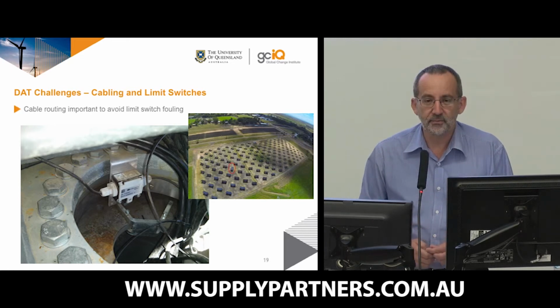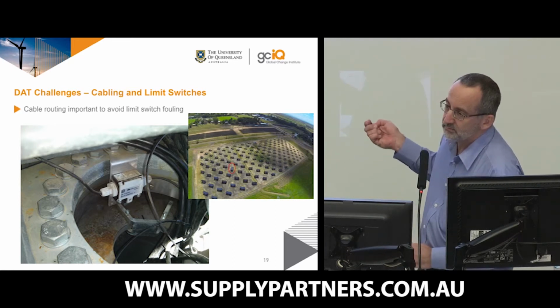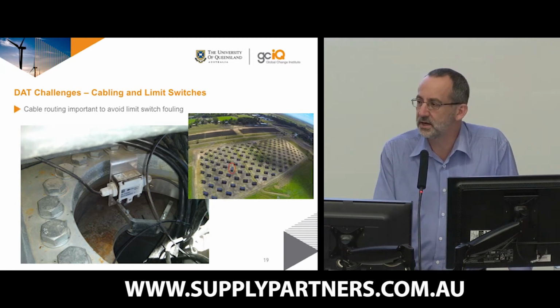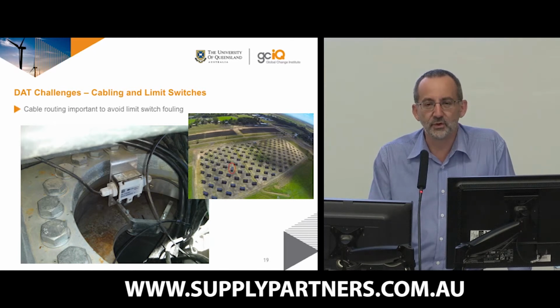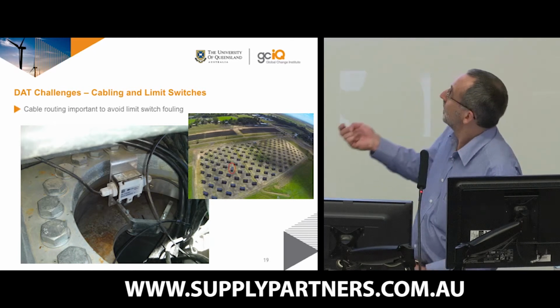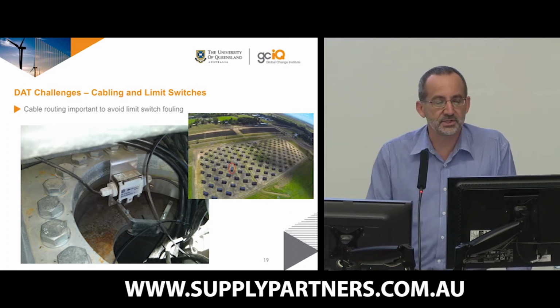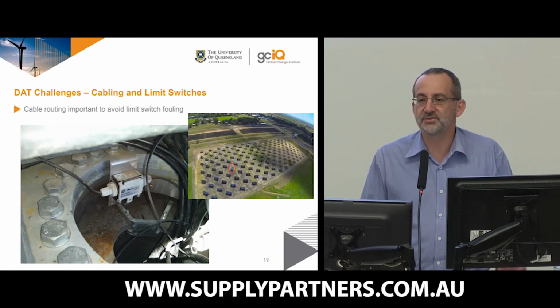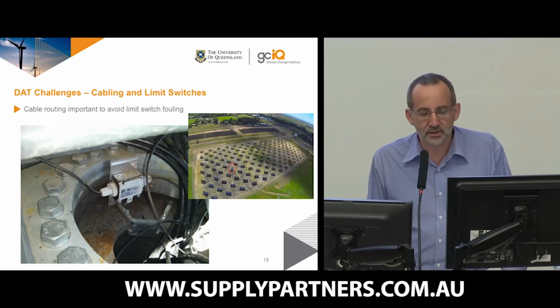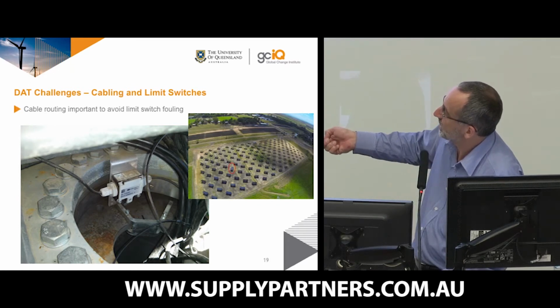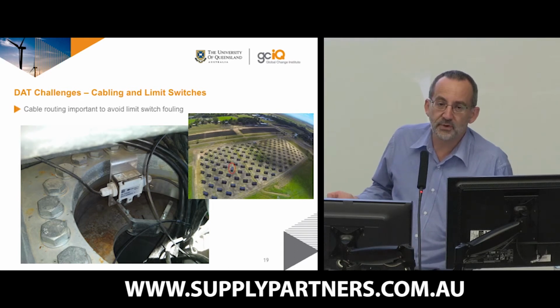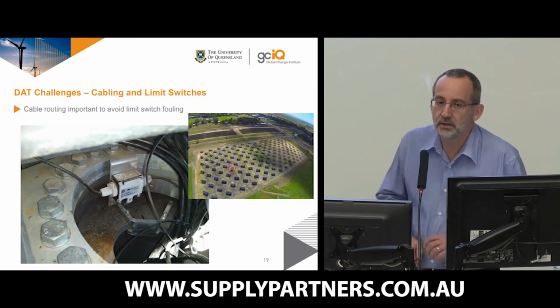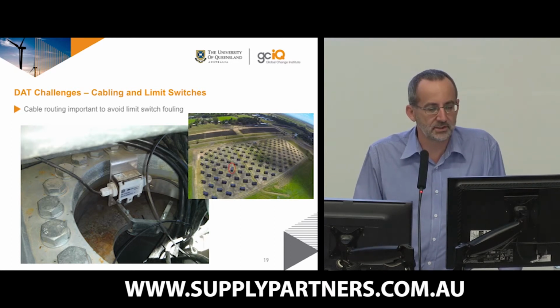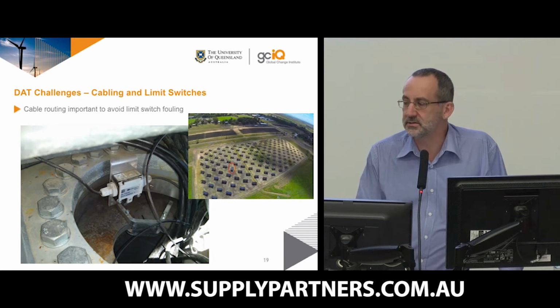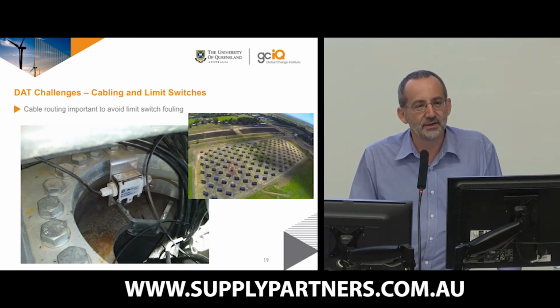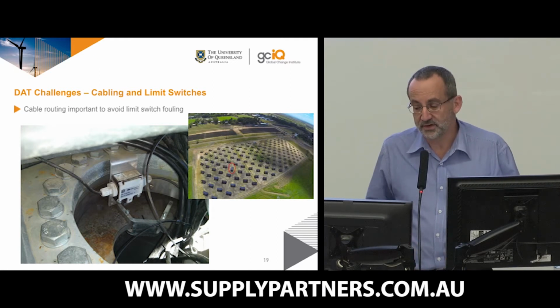The dual-axis trackers have posed a few challenges. If you look at the picture at the back, you'll see the circle unit is not actually facing the same way as all the others. Those trackers have quite a few cables running up through the mast, and in the middle of that you'll see a limit switch, which is designed to tell the tracker when it's reached the end of the travel. That particular one's actually installed in the wrong spot. It's supposed to be on the outside of that boomerang rather than the inside. But what we did find was happening is that all these cables running up through the middle were fouling the limit switch and causing it to stop. And as a result of that, unfortunately, our dual-axis array has been stowed since March and is still waiting remedy. So that has proved an interesting challenge.